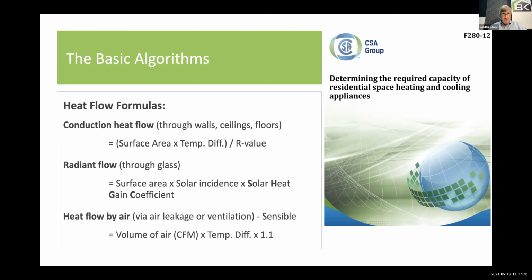To remind yourself, just from straight, let's say, grade 6 math, you can start to imagine conduction heat flow. If I double the surface area, I'm going to double the heat flow. Right? If I double the R value, I'm going to cut the heat flow in half. So if you really wanted to have a smaller furnace, you would make smaller houses, less surface area, and you would put more insulation in. You would double the R value, or triple the R value, and away you would go. So those are the basic formulas that are used in CSA F280. We used to do these manually. Now all of these are built into spreadsheets and we do them automatically. But these are the design heat loads and heat gains that we want to speak of.